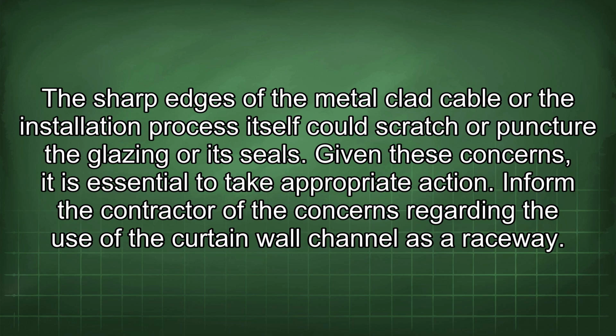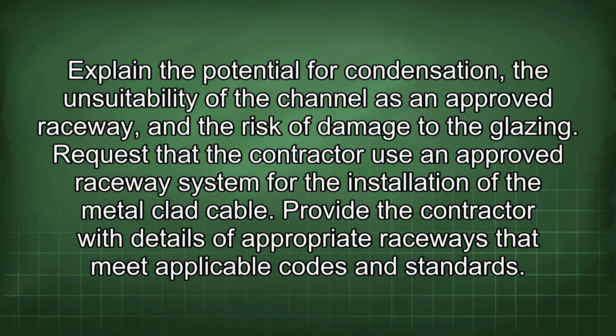Given these concerns, it is essential to take appropriate action. Inform the contractor of the concerns regarding the use of the curtain wall channel as a raceway. Explain the potential for condensation, the unsuitability of the channel as an approved raceway, and the risk of damage to the glazing. Request that the contractor use an approved raceway system for the installation of the metal-clad cable.